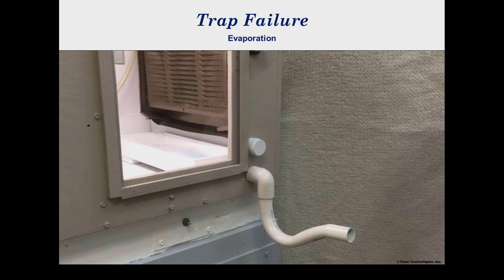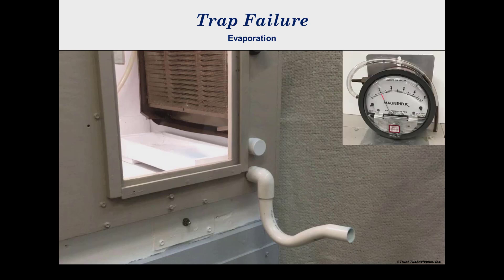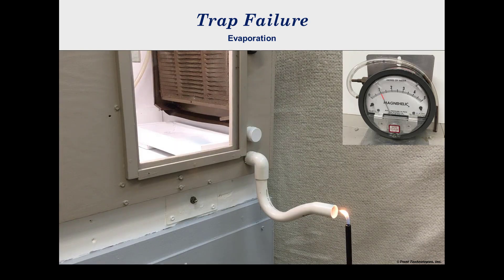With the best possible trap geometry, the effect of evaporation is illustrated with an empty trap. The laboratory simulator is being operated with a negative one inch of water pressure. Systems are often operated at this or more negative pressures. During startup after a heating cycle like for summer cooling, trap water is evaporated, allowing air ingestion.